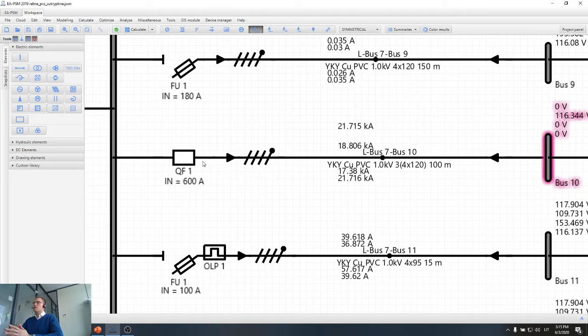However, if for example we have very long cables and the short circuit current will be close to, let's say, the nominal level of the protection device, then our protection device will not be sensitive enough. So the sensitivity principle will not be maintained. And usually this happens when we have single line short circuits, so one phase short circuits, because of, for example, a high impedance path from the short circuit location to the transformer. One phase short circuit current can be very small, and our protection device can be not sensitive enough to find this kind of short circuit. So the first principle is sensitivity.